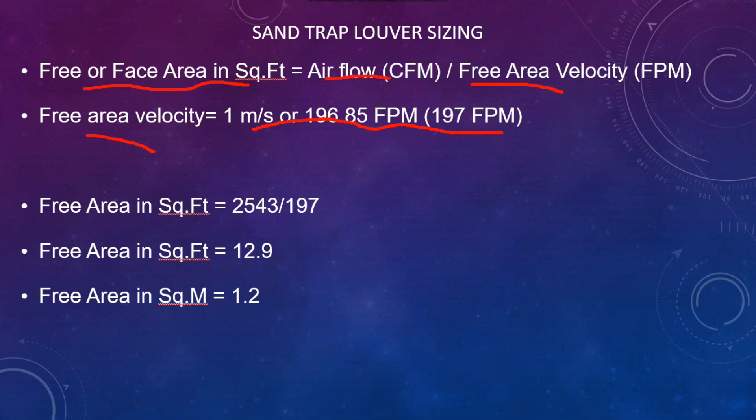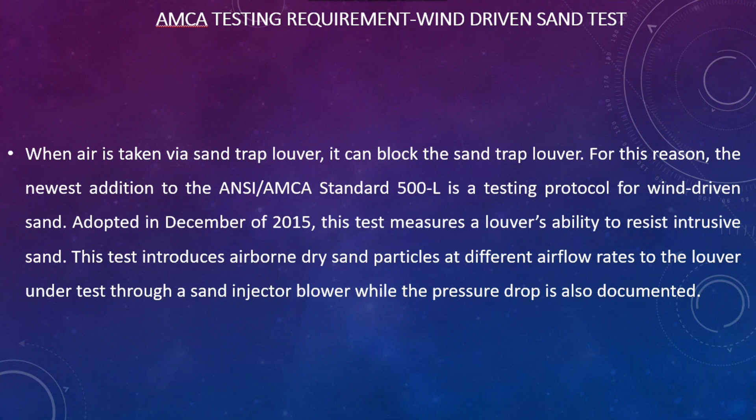We need to understand where this 1 meter per second comes from. For that we have to look into the AMCA standard testing requirements. AMCA — the Air Movement and Control Association — performs 5 different types of tests for louvers. The different test requirements and laboratory arrangements were explained in my last video on fresh air louver sizing. Please watch that video; I have given the link in the description.